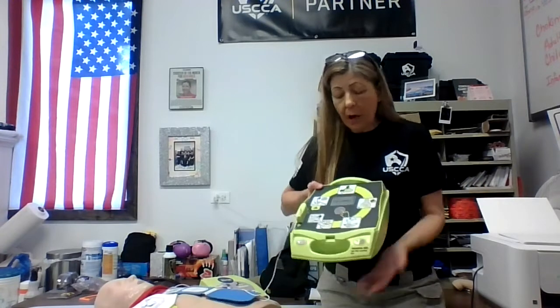I'm going to shut that down. You would never turn those off. Just leave it on. It's going to stay on the entire time, whether they need a shock or not. It's going to keep coaching you through CPR. The other automated external defibrillators on the market do not have that coaching ability, but they all do talk to you. They all have that beeping sound on them for you to follow the speed. This one's just a little bit more product, offers some more. And I really like it because this is what the fire departments are using. When they show up on scene, this is the product they have. When they arrive, we may not have remembered how many times the shock's been applied.